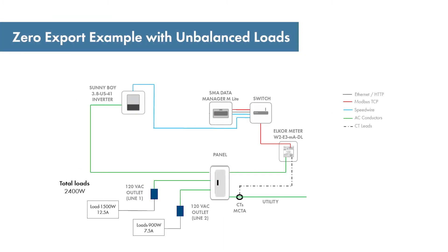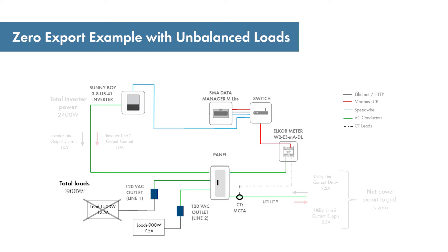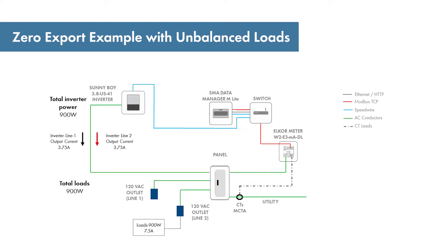One technical point to clarify is exactly what zero export means for this system. An SMA inverter will output balanced current on its output AC line conductors. If the load demand is not balanced across those lines, zero export will yield net zero power flowing to the grid. However, at the point of interconnection, one line will be importing power from the utility and one line will be exporting power to the utility. It is the responsibility of the system operator to ensure that all utility requirements are satisfied under all operating conditions.